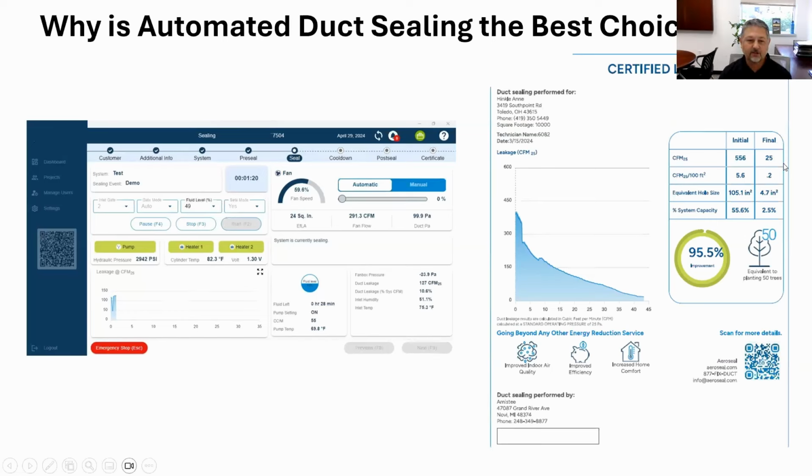And then during the seal process, the sealant is injected by a nozzle that's used specifically for the system, and atomized with compressed air into the system and conducted into the ductwork. Physics takes over from there, right? These atomized sticky particles of polymer are driven to the leak points. It doesn't coat or encapsulate the duct system. It's going specifically to the leaks, right? And the system monitors all that on a dashboard throughout the seal process.